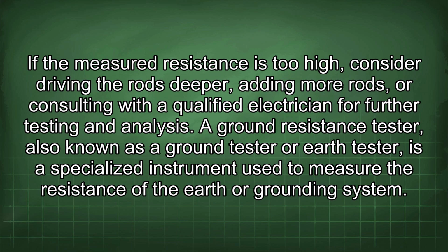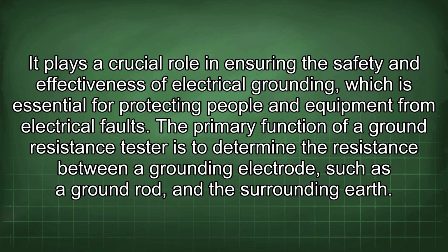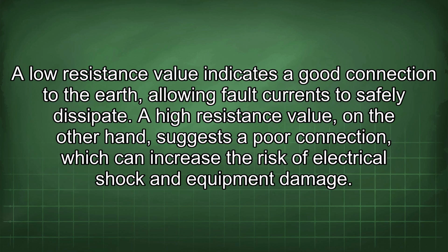A ground resistance tester, also known as a ground tester or earth tester, is a specialized instrument used to measure the resistance of the earth or grounding system. It plays a crucial role in ensuring the safety and effectiveness of electrical grounding, which is essential for protecting people and equipment from electrical faults. The primary function of a ground resistance tester is to determine the resistance between a grounding electrode, such as a ground rod, and the surrounding earth. A low resistance value indicates a good connection to the earth, allowing fault currents to safely dissipate.